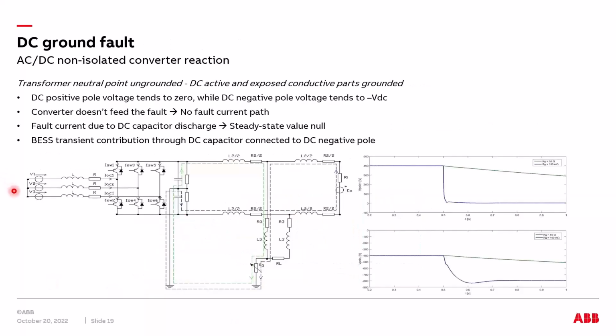In case of isolated AC transformer windings, and we have a connection, for example, of the DC midpoint to the ground, in this case we don't have the converter contribution to the ground fault anymore, but we have a transient contribution coming from all the other batteries installed in parallel, and if we also have the photovoltaic system connected, or any other DC sources with a non-isolated interface converter. But we have a negligible steady-state ground fault current.